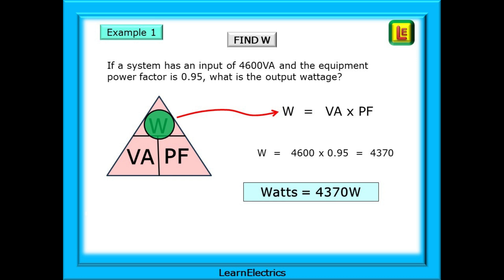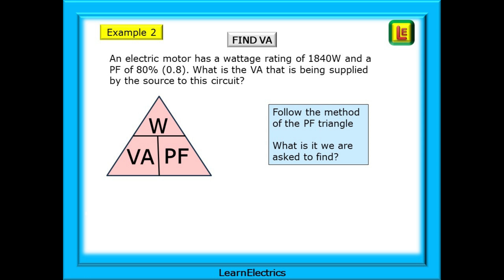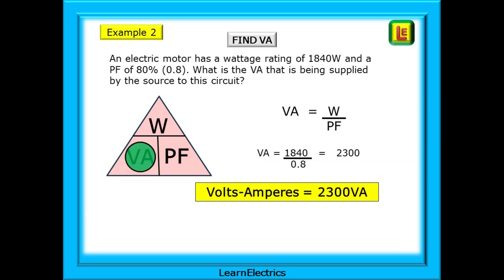Example 2 — find VA: an electric motor has an output wattage rating of 1840 watts and a PF of 80%, or 0.8. What VA is being supplied by the source? Since watts is known, VA must be more than 1840. VA equals 1840 divided by 0.8, which gives 2300 VA.